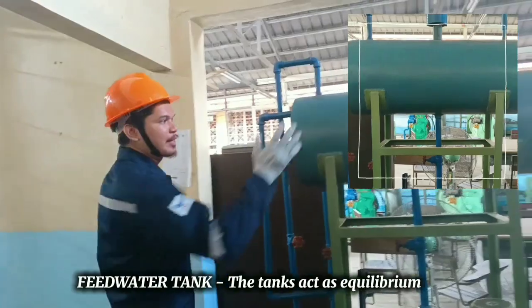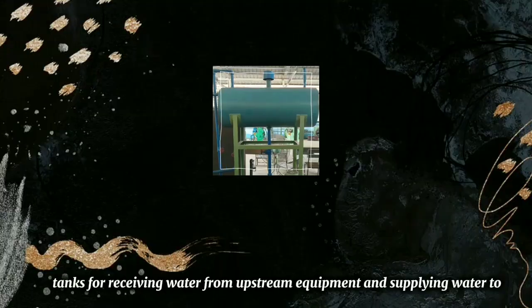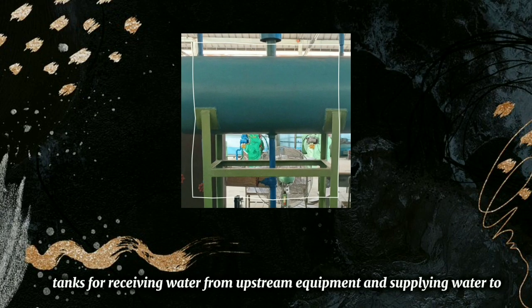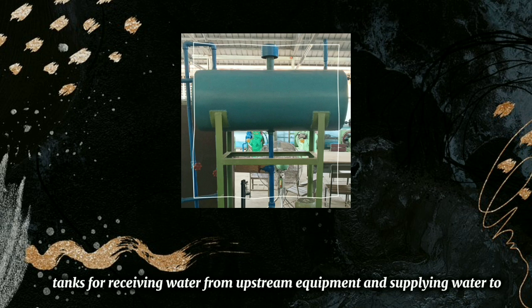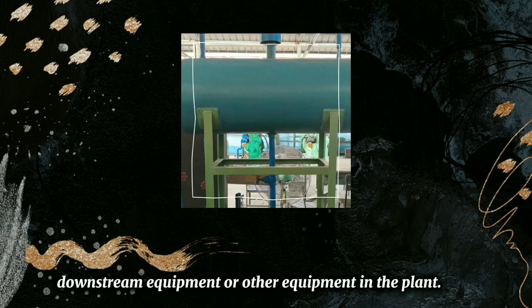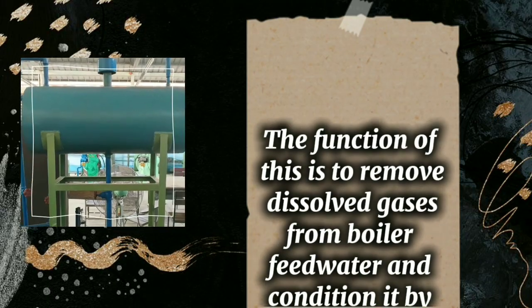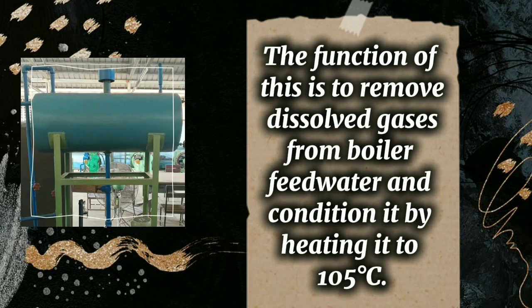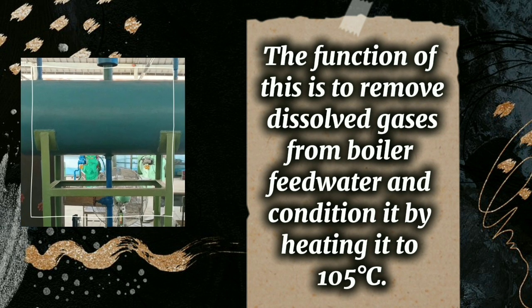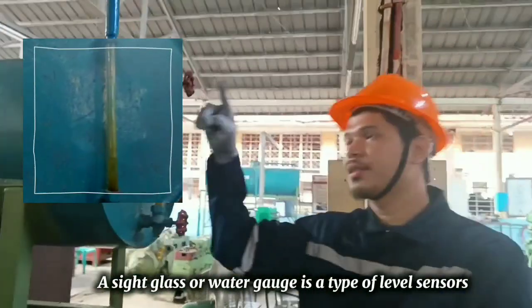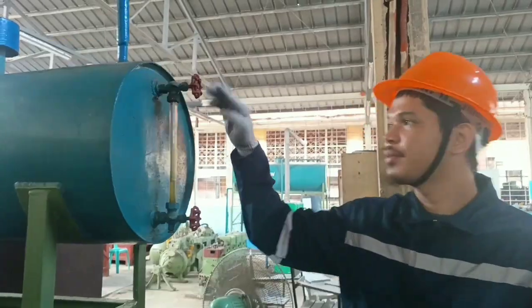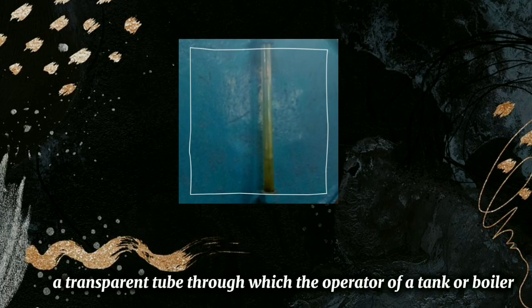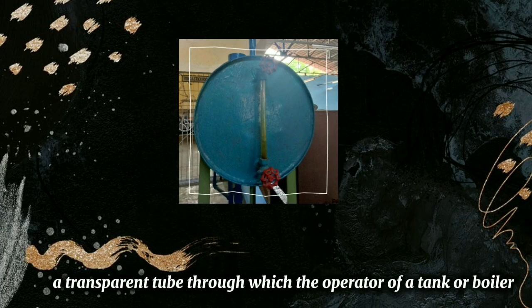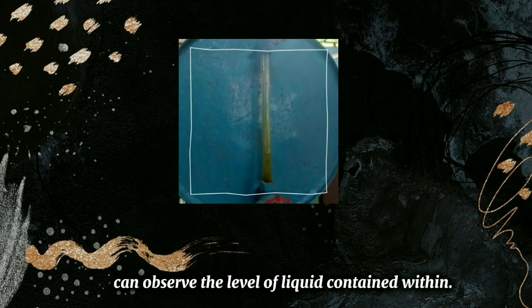Feedwater tank. The tanks act as equilibrium tanks for receiving water from upstream equipment and supplying water to downstream equipment or other equipment in the plant. The function of this is to remove dissolved gases from boiler feed water and condition it by heating it to 105 degrees Celsius. A sight glass or water gauge is a type of level sensor, a transparent tube through which the operator of a tank or boiler can observe the level of liquid contained within.